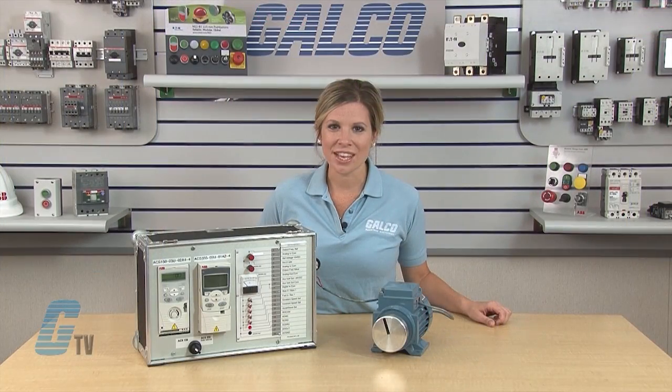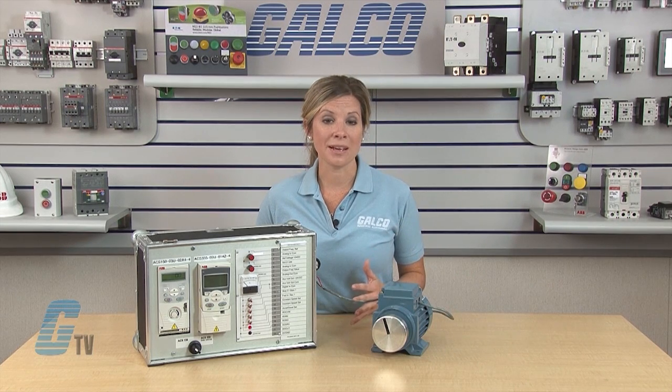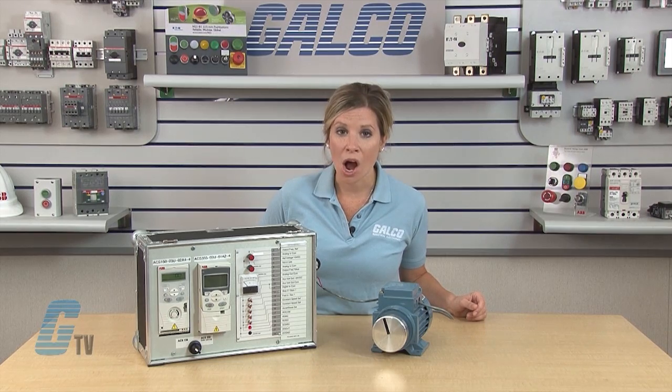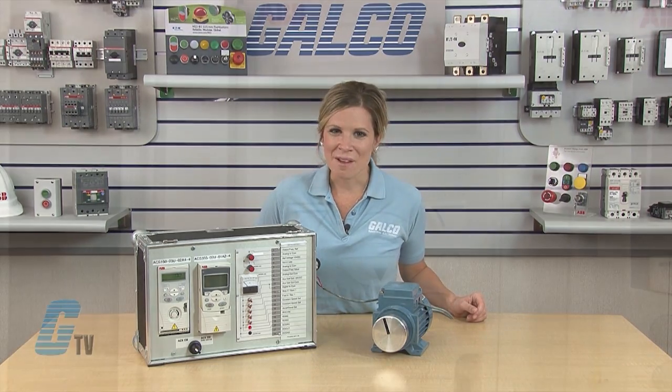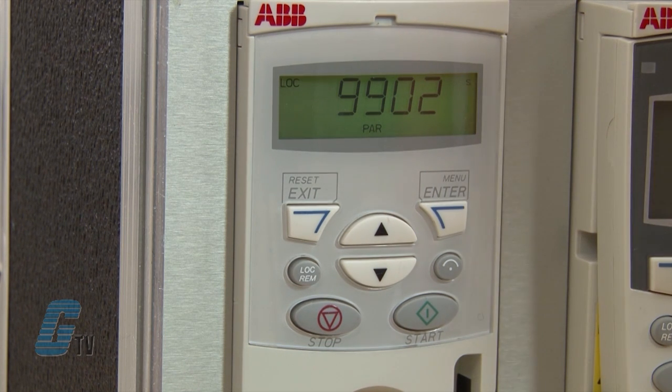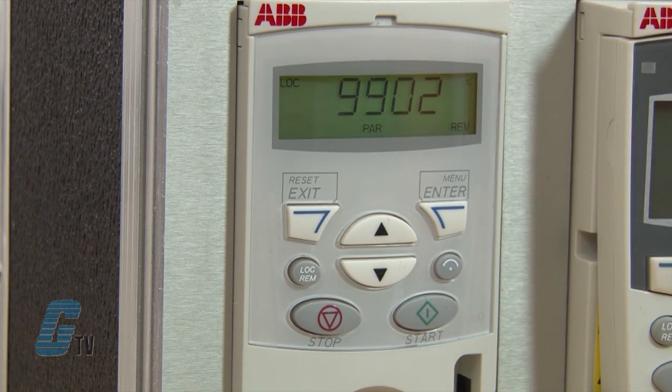The menu and enter key are both the same and labeled on the basic control panel. In the parameter menu, the bottom left will now display PAR for parameter. My first parameter is 9902, which sets the application macros. This is application specific and should only be altered if required. Some of these applications include PID control, two wire start stop, motor potentiometer, and torque control.